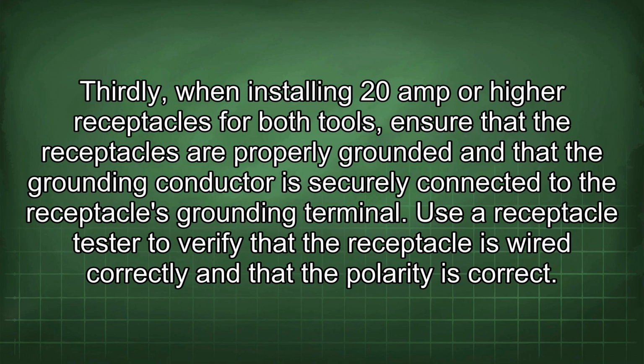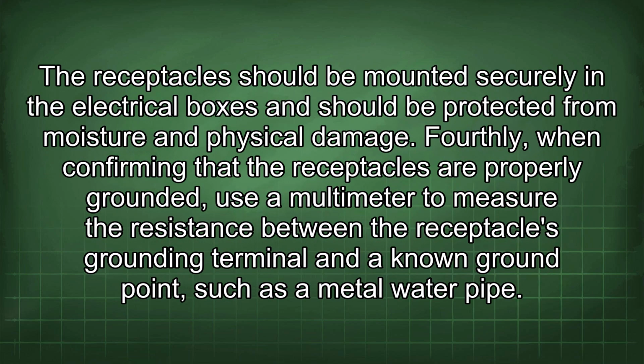Thirdly, when installing 20-amp or higher receptacles for both tools, ensure that the receptacles are properly grounded and that the grounding conductor is securely connected to the receptacle's grounding terminal. Use a receptacle tester to verify that the receptacle is wired correctly and that the polarity is correct. The receptacle should be mounted securely in the electrical boxes and should be protected from moisture and physical damage.